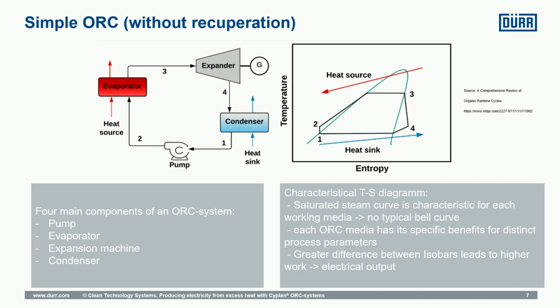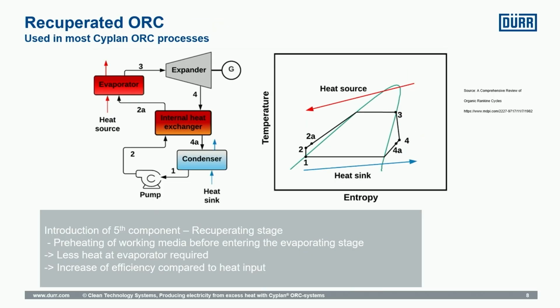With the ORC working media, you see it here on the side where it's 3 and 4 - when we are expanding, we are always in the dry area. This makes it somewhat unique, because it's a kind of fail-safe mechanism in the technology itself. So it's very sure that the turbine, or whatever is there, doesn't see droplets, and you do not have any problems on that side.